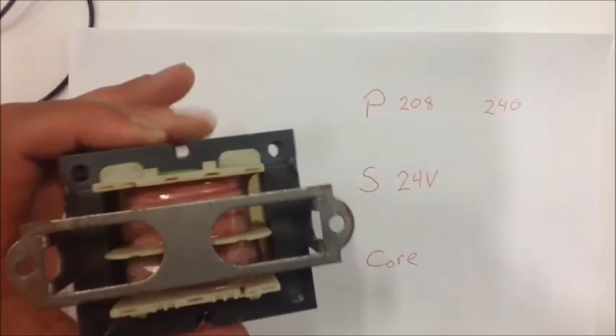Or what this one's designed for is it's going to transform down, it's going to step down, so it's going to take a high voltage and make that magnetic field, and we're going to create a lower voltage source. One other thing to note is the resistance of these windings should always have some resistance. So if I measure the 208 volt portion of the primary winding, I'm looking at 32.3 ohms.